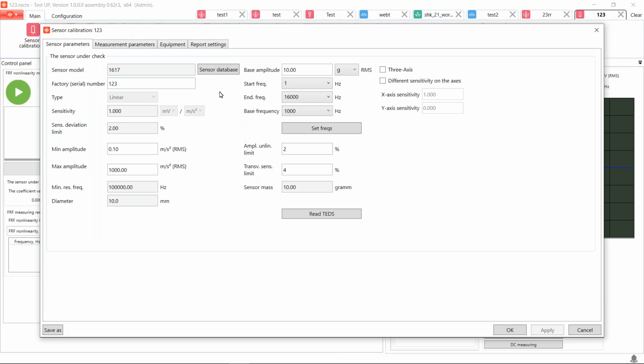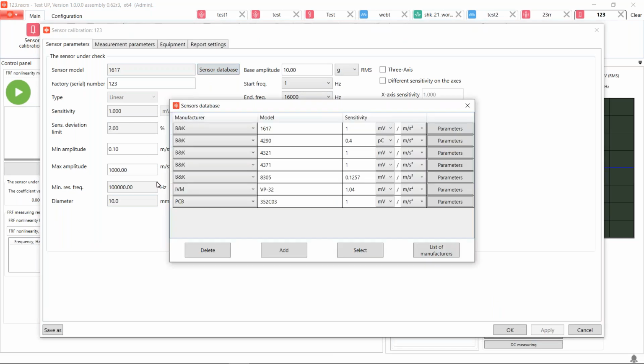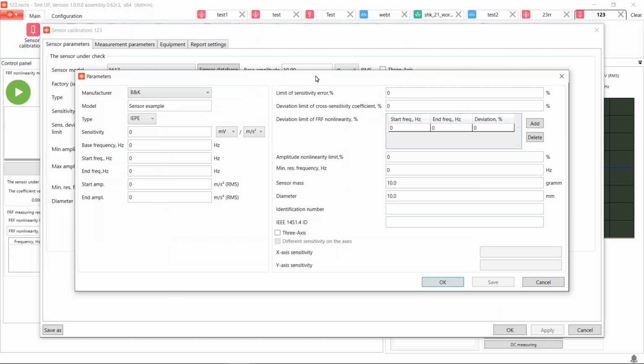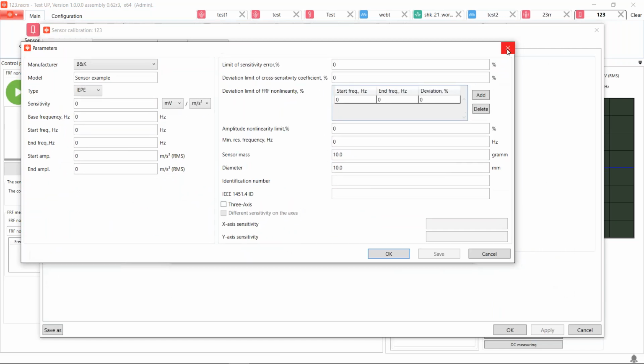Where I would like to draw your attention is Open Sensor Database. Here you have the database of available manufacturers and sensor models. The database means that we have already put all of the parameters of sensors in accordance with their passports in our software, so you don't need to enter anything. But in case you don't have the sensor you need for the calibration procedure, you can simply click on the Add button and add the parameters you need for your sensor in accordance with the passport.